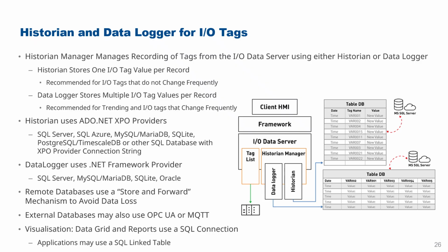So if you're using a historian, it stores one IO tag value per record. And the reason for doing this is it can potentially give you more columns with more information, but what it does mean is that maybe the performance is reduced because each record is calculated as an individual transaction. So it's one IO tag per transaction or per record. So it's recommended for IO tags that do not change frequently, but it also gives you additional capabilities like storing previous values. So for 21 CFR 11 validation, you can do things like make sure that the new value and the old value are correlated and you haven't missed any values.